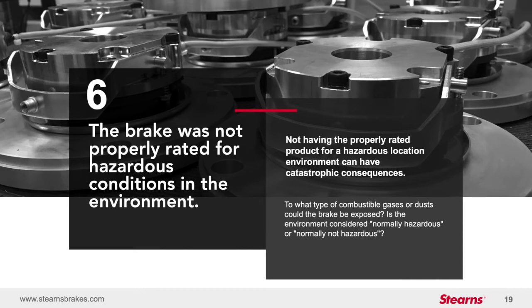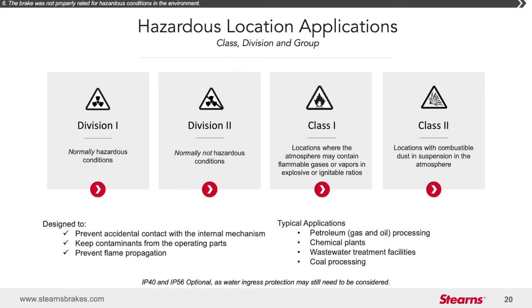The next few slides will be breaking down the area classifications that account for dangers presented by different types of explosive conditions and enable protective measures to be taken which account for both cost and safety. The National Electrical Code, or NEC, establishes area classifications based on divisions, classes, and groups, which are factors combined to define the hazardous conditions of a specific area. As shown below, the division defines the likelihood of hazardous material being present in a flammable concentration.